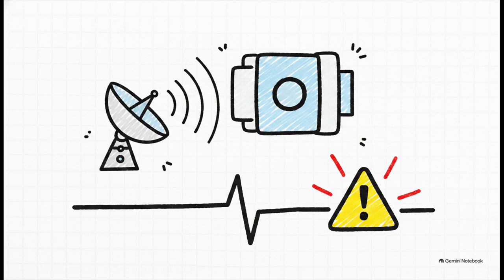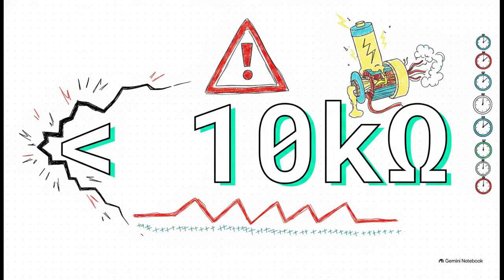It's exactly like an early warning radar, calculating the high-voltage isolation resistance in real time. If that resistance dips under 100 kiloohms, which is about 500 ohms per volt, the system flags a level 1 warning. It knows for a fact that something inside the insulation is starting to degrade. But the absolutely crucial point here is this fatal threshold, 10 kiloohms. If the resistance plummets below this number, it means a severe breakdown is imminent. The system has to trigger an immediate severe fault interrupt to prevent a catastrophic short circuit, or worse, a literal explosion. Every single millisecond counts here.